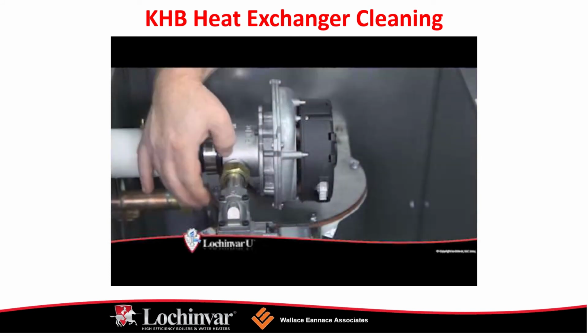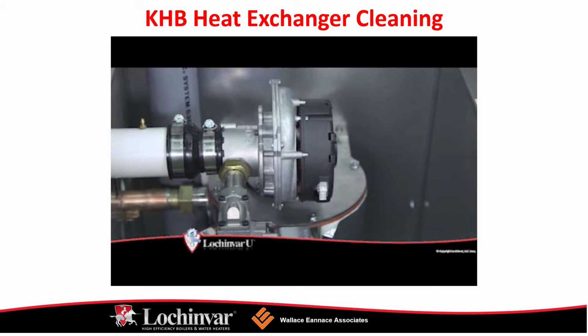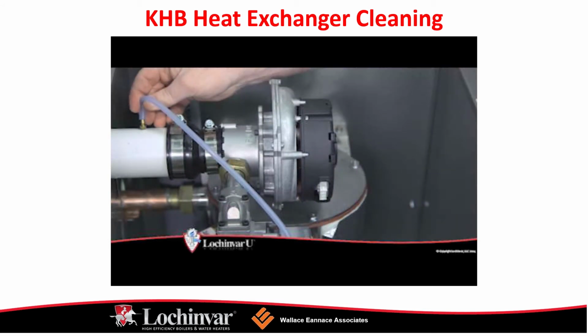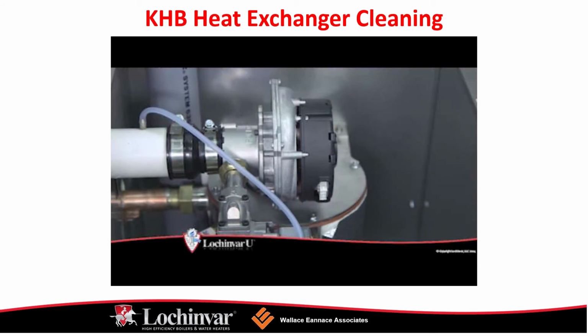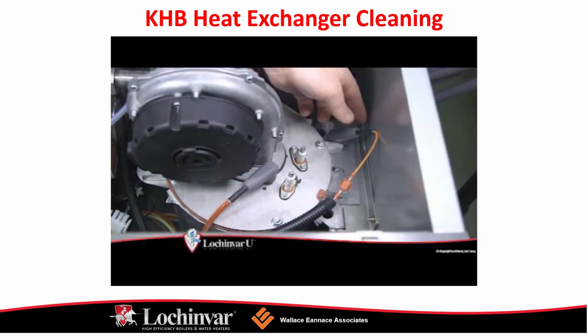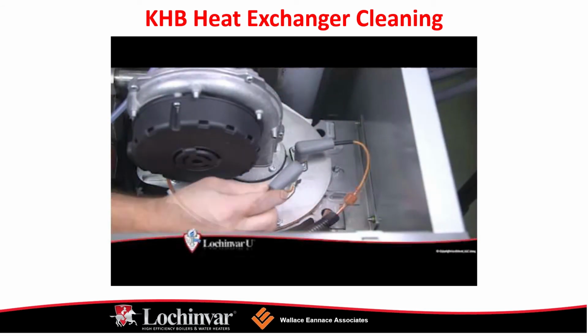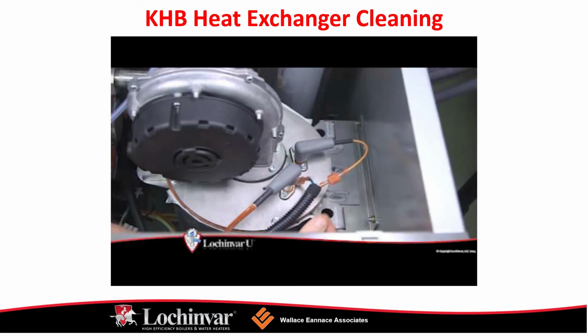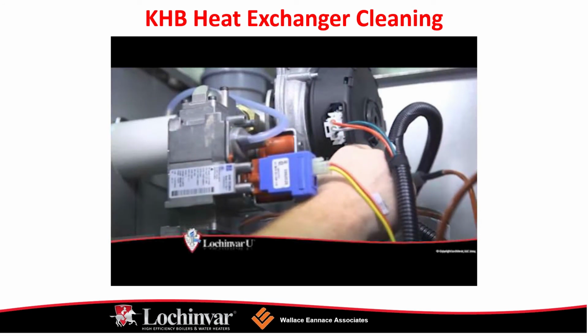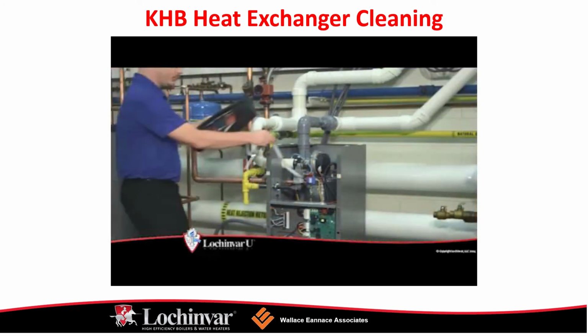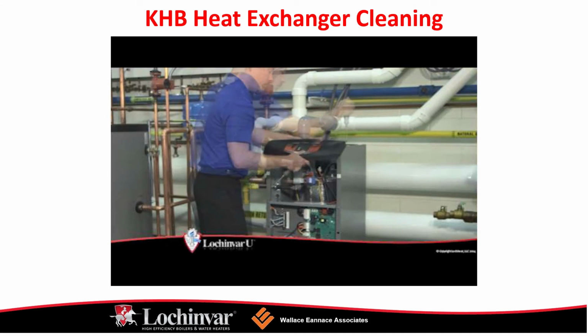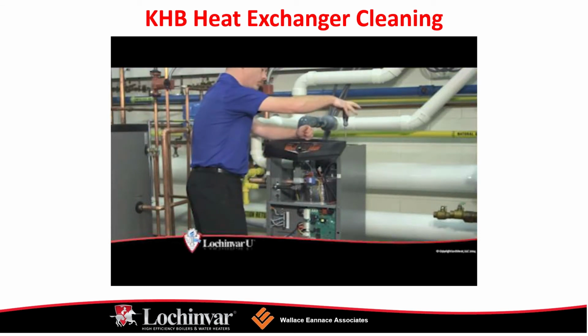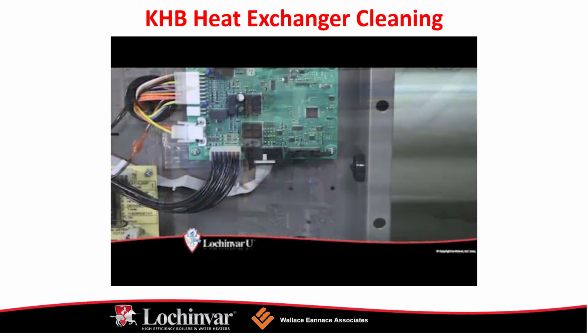Locate and remove the condensate drain line from the condensate trap and route directly to a drain. Inspect the heat exchanger surface and combustion chamber wall for any soot deposits or dirt accumulation. Using a vacuum cleaner, remove any loose debris from the heat exchanger. Brush the heat exchanger surface, flue tube entry points, and the combustion chamber wall with a nylon brush. Then re-vacuum the heat exchanger to remove debris. And rinse the debris from the heat exchanger with a low-pressure water supply.